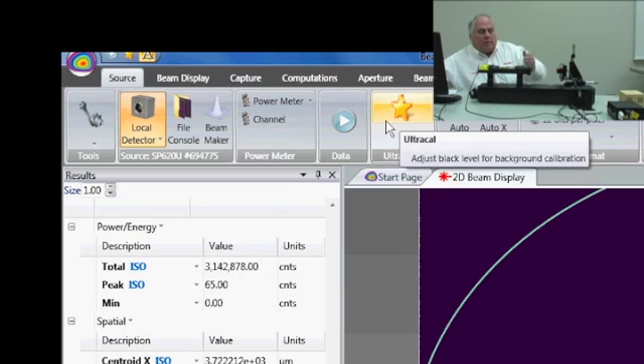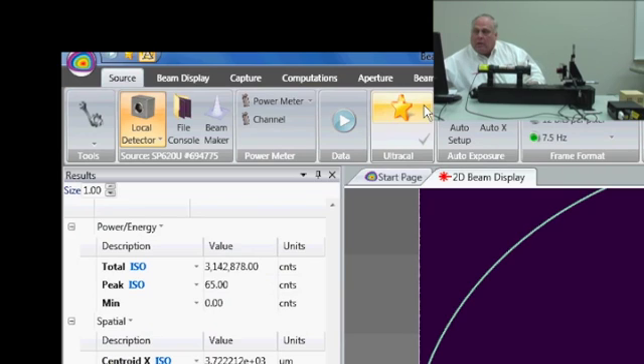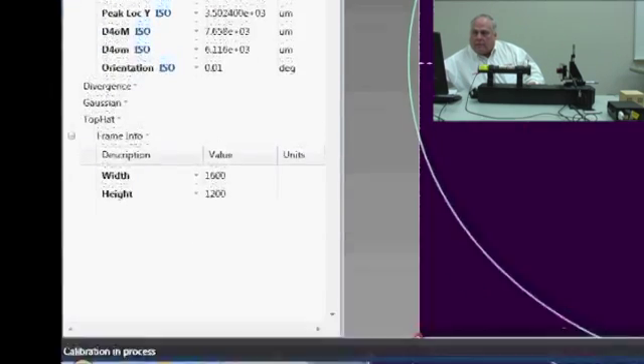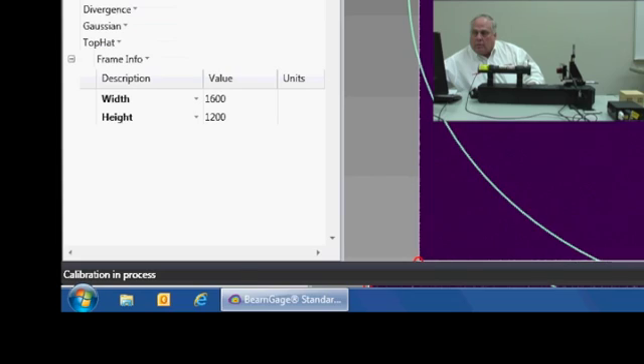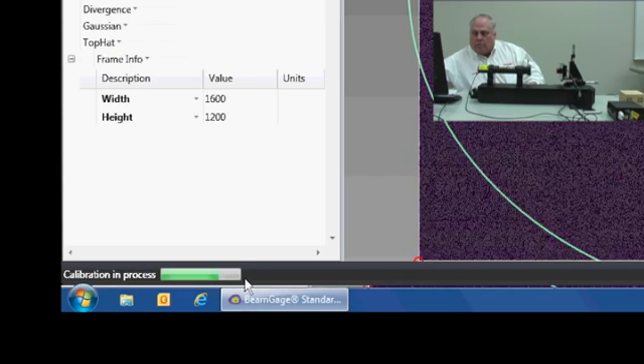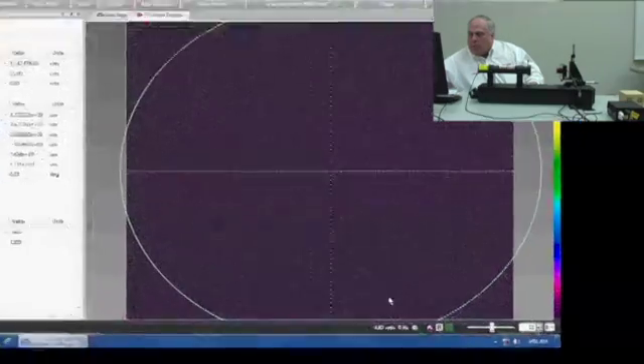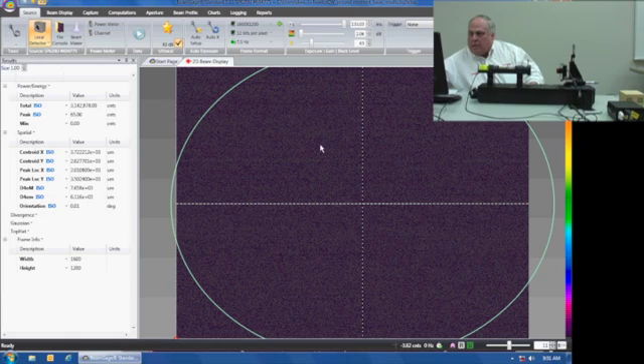Next thing I'll do is I will block the beam. We've already got the attenuation set up for the camera based upon the laser power, and right here is the UltraCal GUI. You'll punch on that, and we'll simply wait for it. Down the lower left hand corner, you'll see calibration in process. There's the meters going through, and it's letting you know that calibration is finished. You'll see right down here this green dot that shows that we have an UltraCal, a green square, and you can always look on the picture. It's generally a sandpaper type picture, and it lets you know that you've finished it. That lets us know that the camera's set up and ready to use. Based upon the proper attenuation you've set up, this will work perfectly for you.